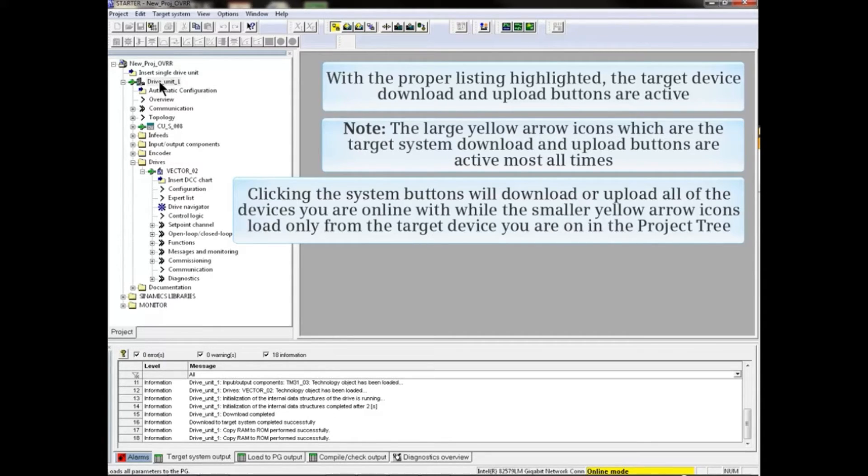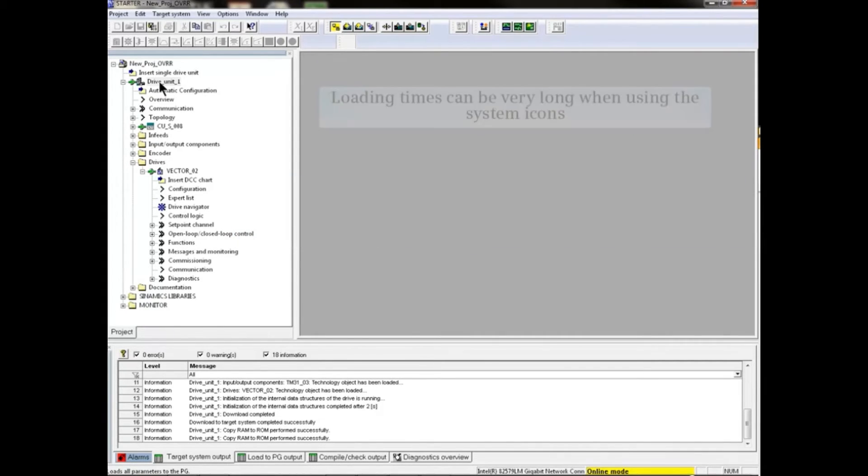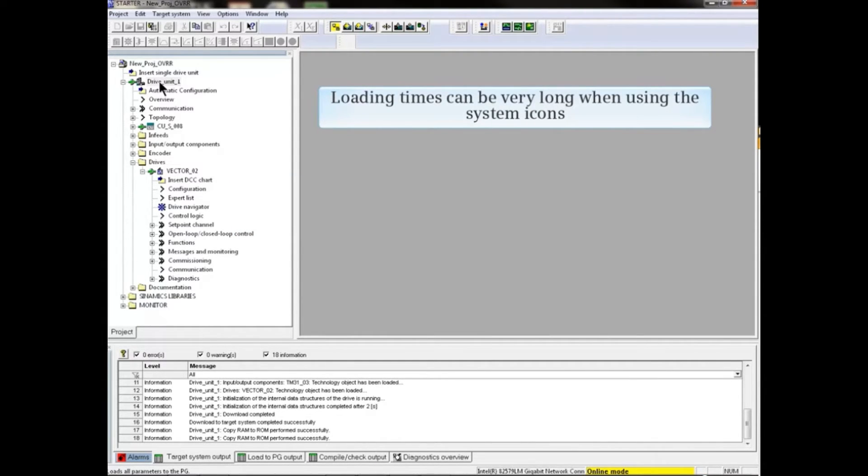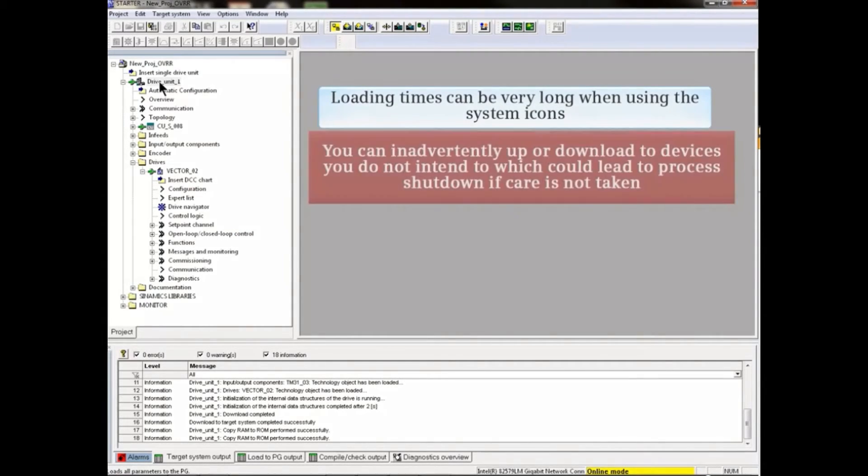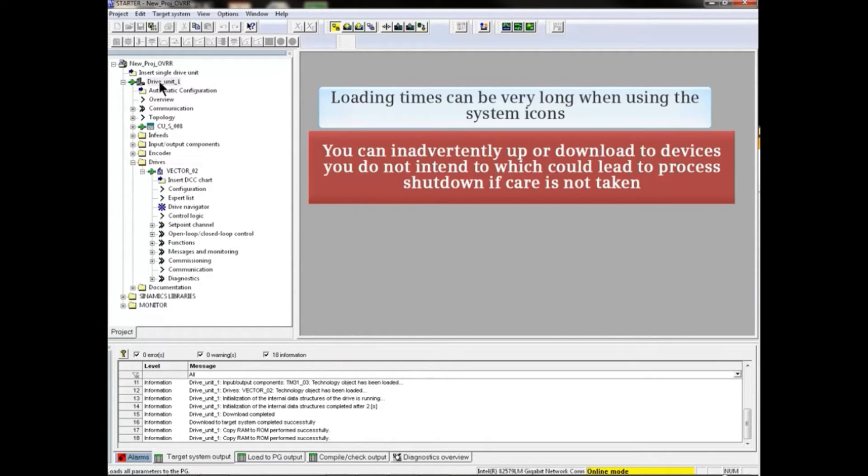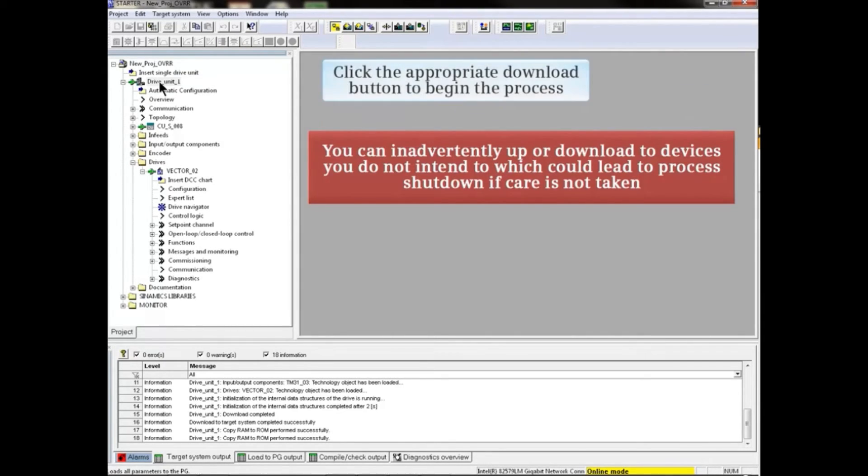Loading times can be very long when using the system icons, and you can inadvertently upload or download to devices you do not intend to, which could lead to process shutdown if care is not taken. Click the appropriate download button to begin the process.